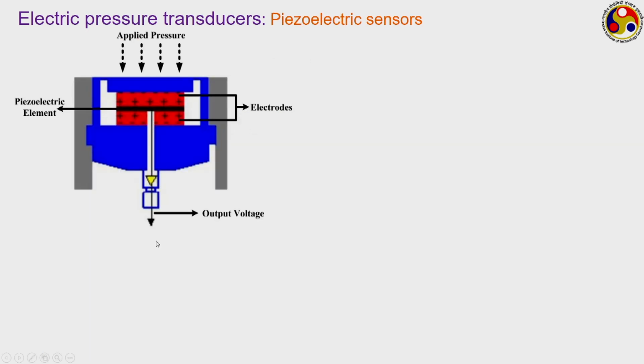Another electric pressure transducer that we can talk about is the piezoelectric sensor. Again, the operating principle is the same as in any piezoelectric device. Here we have some kind of natural or synthetic crystal, which when subjected to a certain force develops polarity, that is, positive ions go closer to one plate and negative ions accumulate closer to the other one. So if we connect them by suitable output circuitry, we are going to get some kind of voltage output. So, this pressure force can directly be related to this voltage output, thereby giving a very easy way of pressure measurement, and we can operate this device over a wide range of pressure from quite small to quite large values.